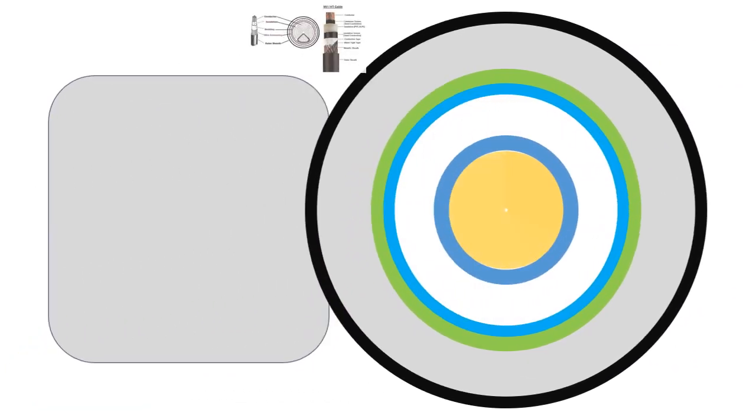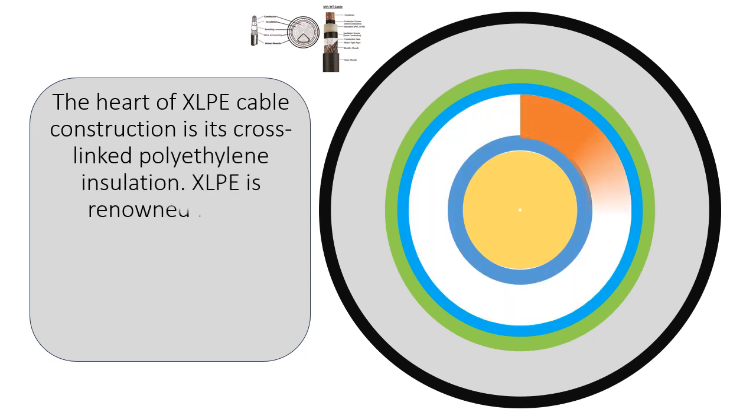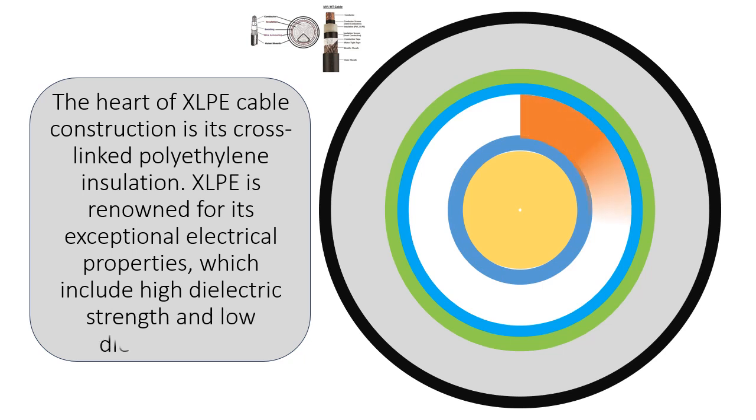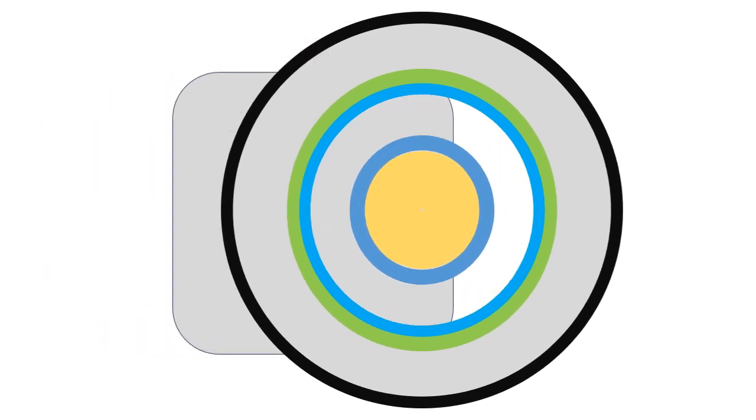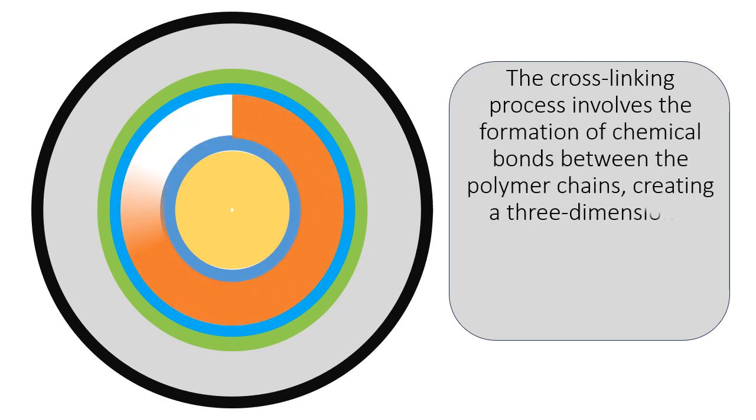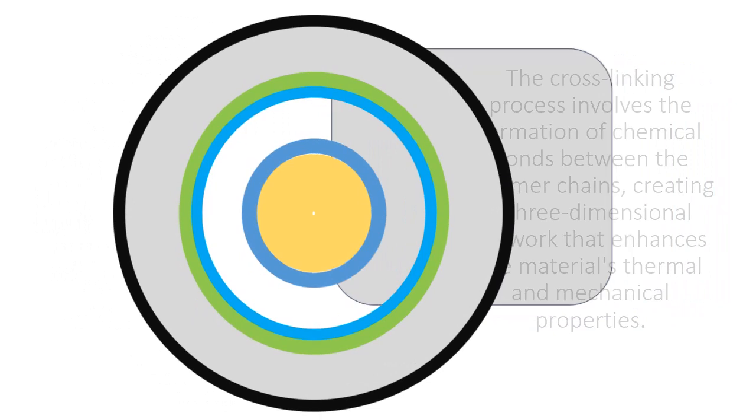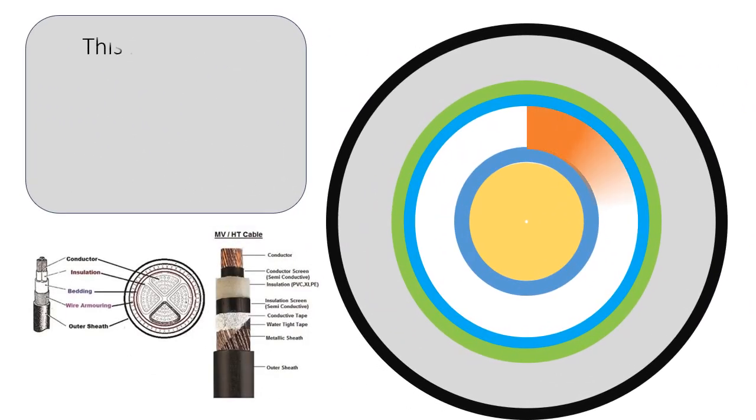Insulation: The heart of XLPE cable construction is its cross-linked polyethylene insulation. XLPE is renowned for its exceptional electrical properties, which include high dielectric strength and low dielectric loss. The cross-linking process involves the formation of chemical bonds between the polymer chains, creating a three-dimensional network that enhances the material's thermal and mechanical properties. This insulation is extruded over the conductor, providing a barrier against electrical leakage and ensuring long-term reliability.